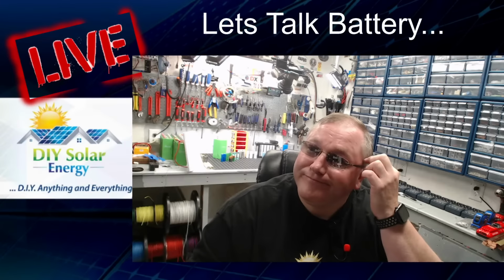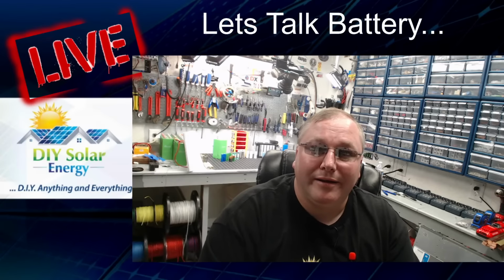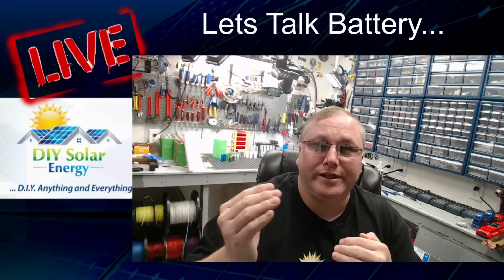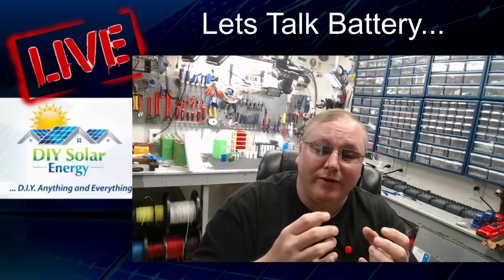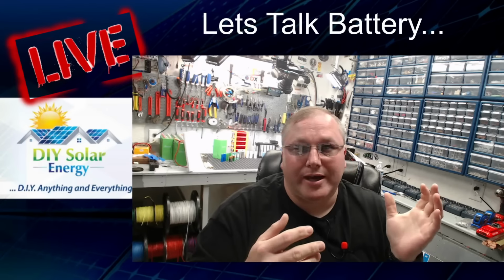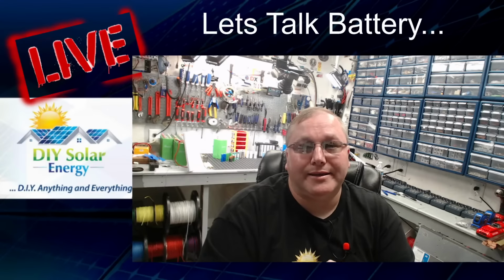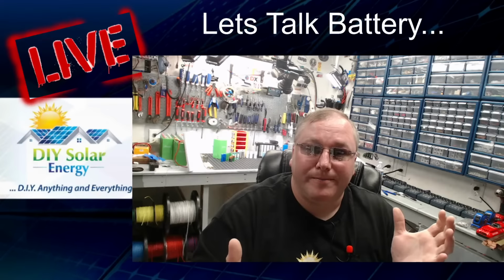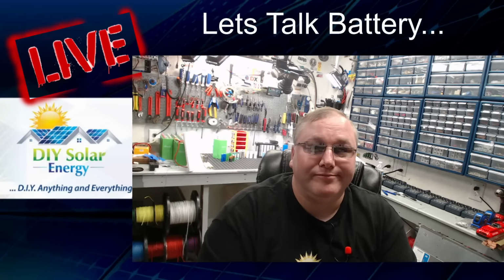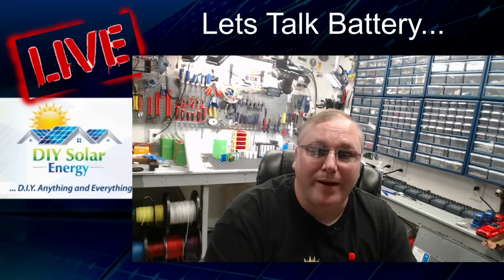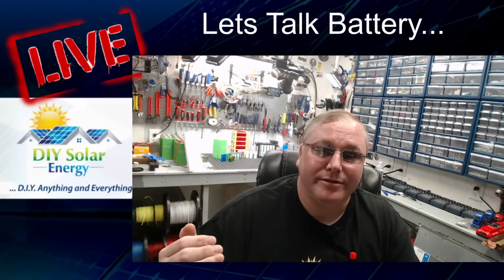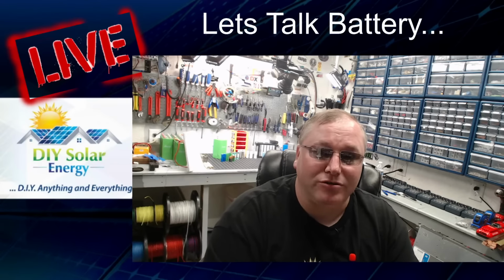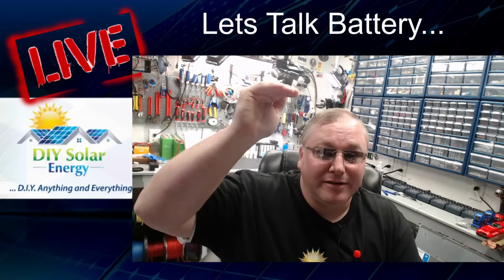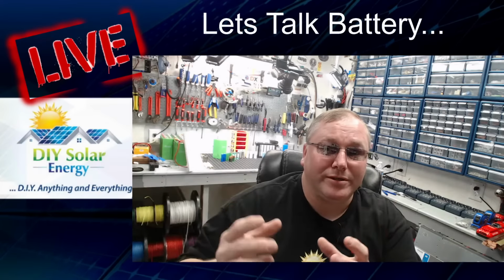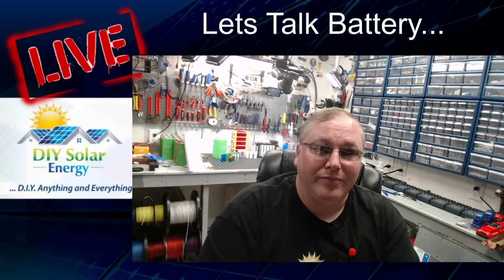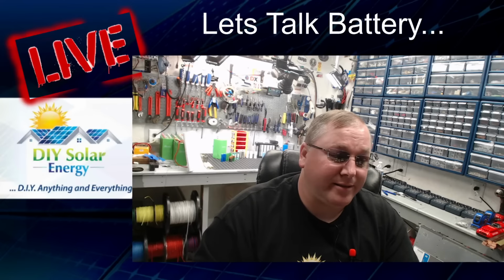...half an acre away, then you're going to have a huge voltage drop if they're lower, because you've got, let's say, 10 panels at 10 amps. That's 100 amps. If you run standard 10 gauge or 8 gauge wire from your panels an acre away to your house, you're going to have a significant voltage and amperage drop. But if you carry that voltage up higher, you're going to be able to use a smaller diameter wire, and your voltage drop is going to be a lot less.